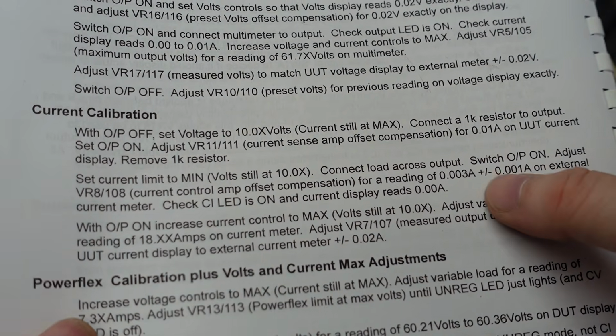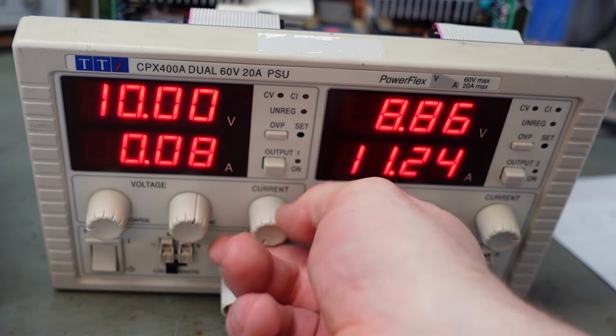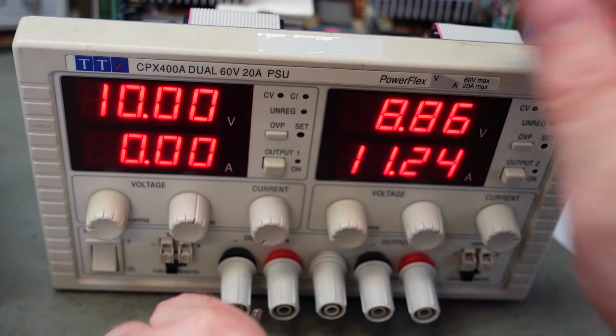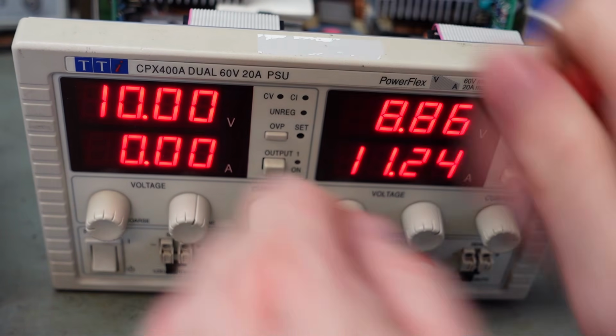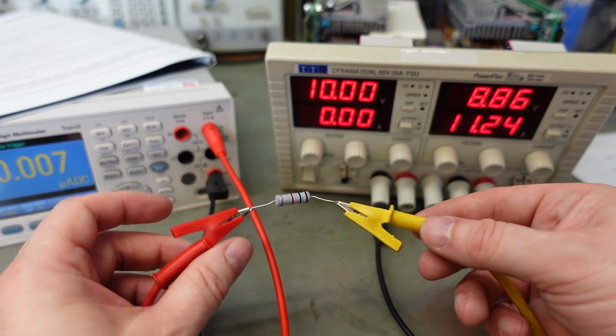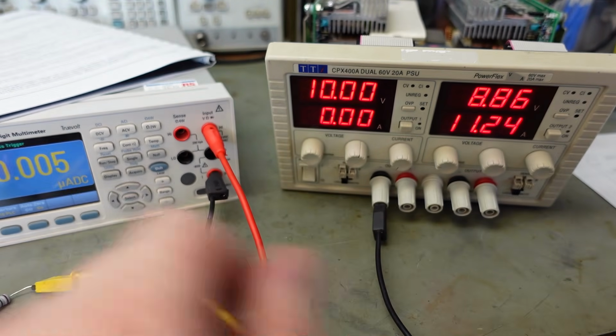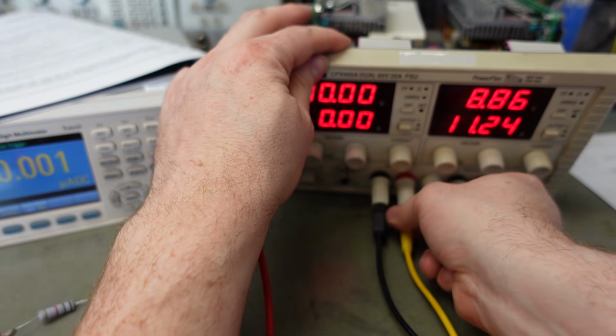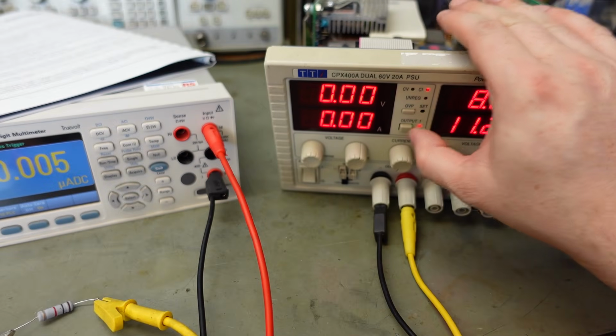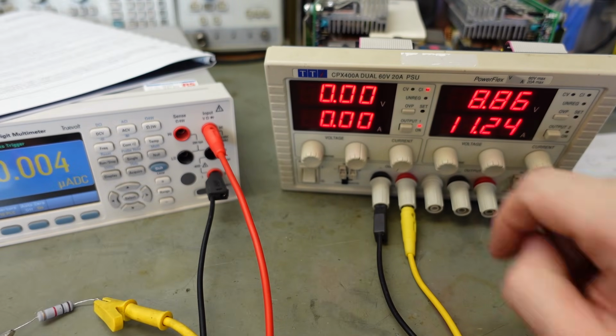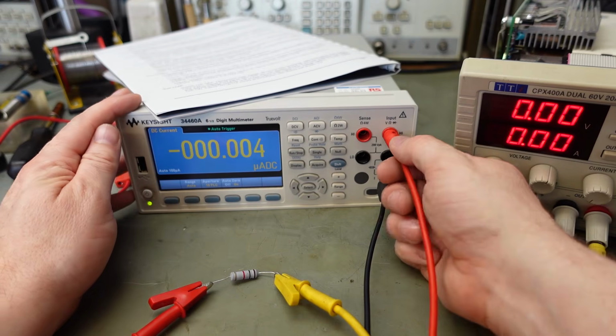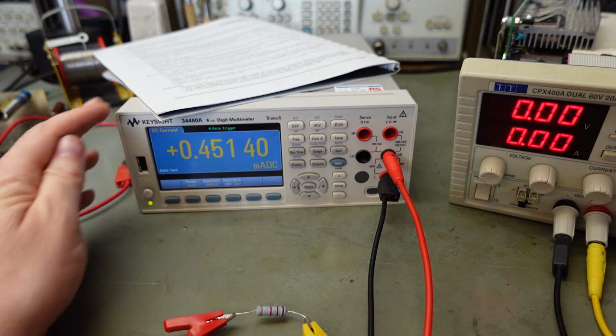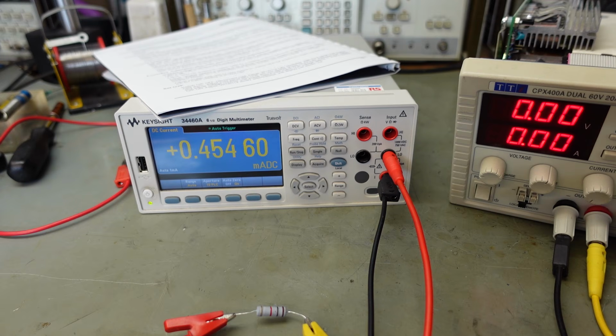The next step is to set the current limit to minimum and check that we've got 3 milliamps. Current to minimum, 10 volts, put the leads in. For the load I'm using the 1k resistor again between these two croc leads. Connect that in there, turn it on. It says it's in current limit, that's encouraging. But I've connected it in the wrong socket, it should go in there. Okay, we got half a milliamp. That's out of spec. VR8, just hiding here.